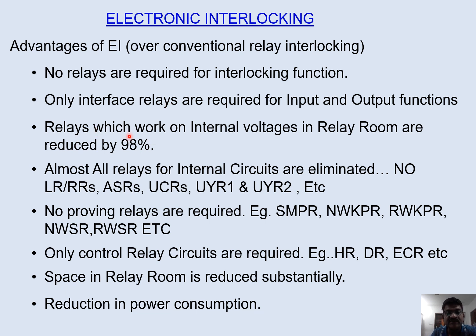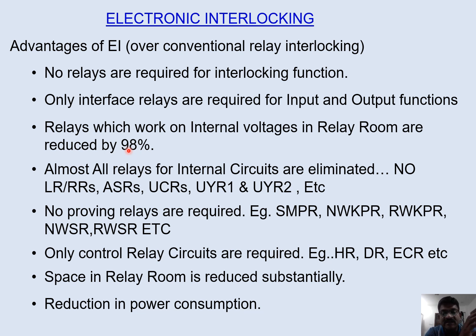Relays working on internal voltages in the relay room are reduced by almost 98 percent. Previously, internal 24 volts were used to pick up many relays — ASRs, UCRs, and similar relays — which are all eliminated because of EI. Hence power consumption has reduced. Almost all relays for internal circuits are eliminated, for example ASRs, UCRs, UYR, etc.